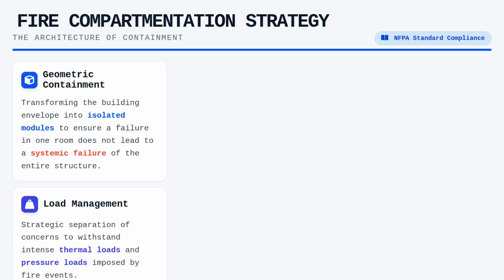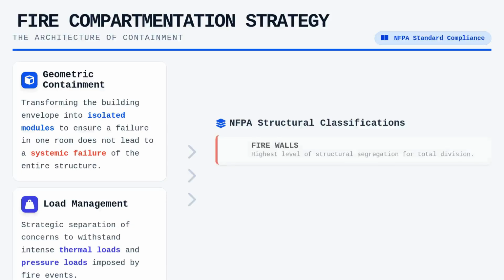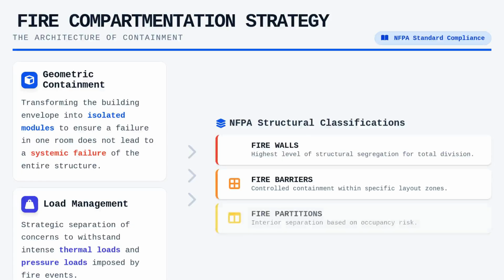The NFPA codes provide the rigorous definitions required to distinguish between firewalls, fire barriers, and fire partitions, each serving a distinct purpose based on the anticipated risk and occupancy classification. By mastering these distinctions, you move beyond mere compliance and begin to understand how the physical layout serves as the first line of defense against catastrophic loss. This is technical, foundational knowledge that every certified fire protection specialist must rely on daily.